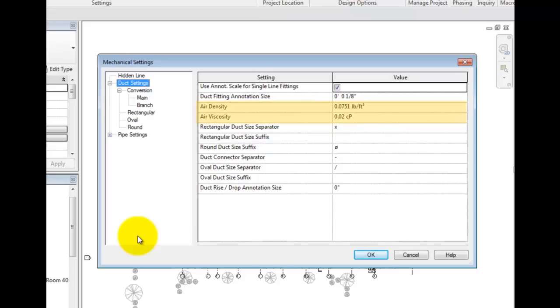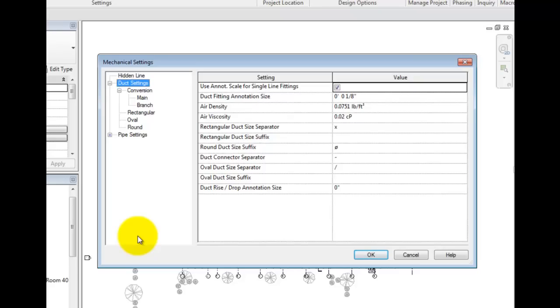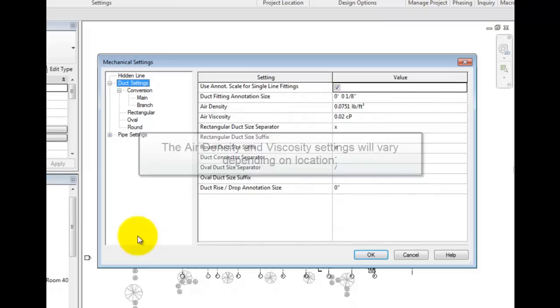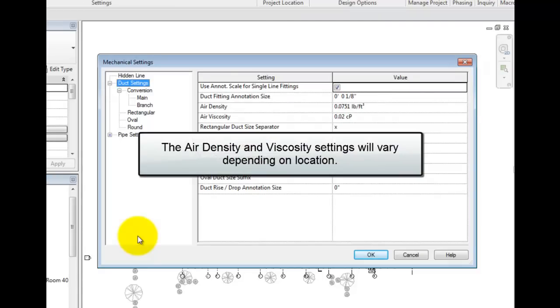The next two settings are very important for air flow calculations. Air density and air viscosity are specified here. These values are used throughout the load and duct analysis engine. These numbers are set at what is standard air temperatures and pressures. If the project is at a higher elevation, say if it's in Colorado, you will need to change these values otherwise everything in the ducts and loads will be off.